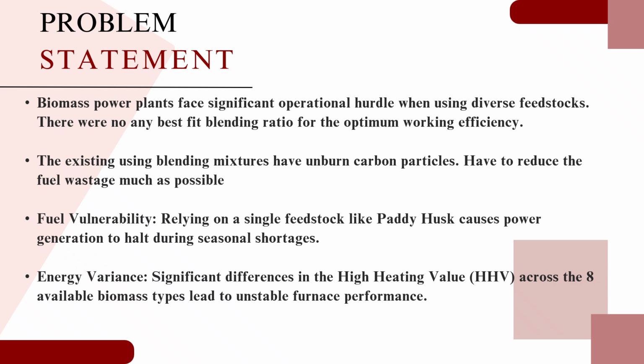Let's discuss the problem statement. Currently, biomass plants face significant operational hurdles when using diverse feedstocks. There is a fuel vulnerability because relying on a single source like paddy husk leads to shutdowns during seasonal shortages. Furthermore, significant energy variance across different biomass types causes unstable furnace performance. Without an optimized blending ratio, we see unburned carbon particles and high fuel wastage.